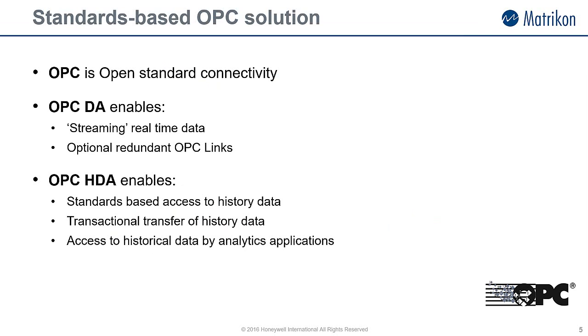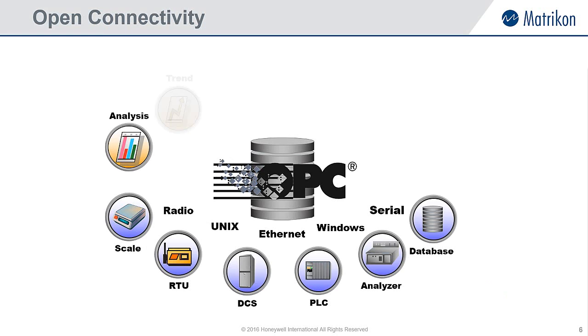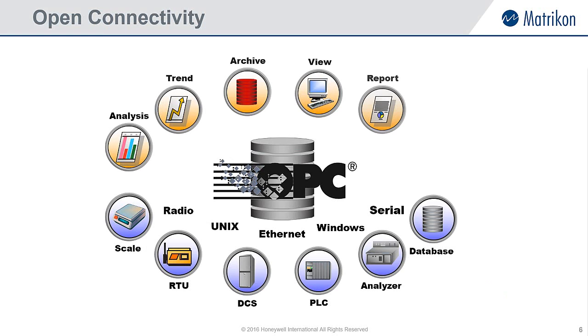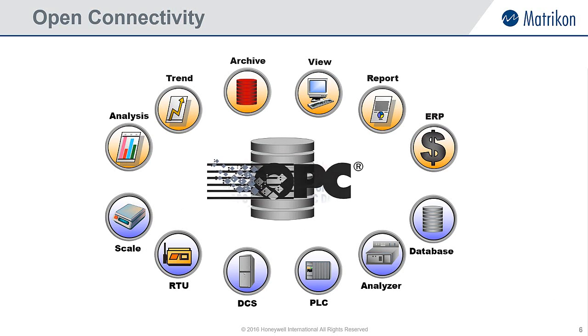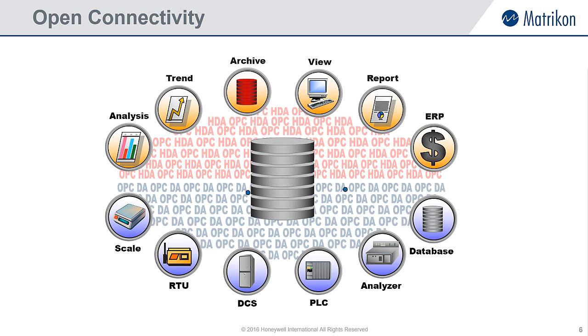We know that OPC allows for open standard connectivity by design. OPC-DA is the specification that covers real-time data access, and OPC-HDA covers historical data access. Utilizing this technology, we can take a better, more open approach to archiving data. Taking the OPC route, we are not locked into specific vendors for real-time drivers or analytic tools.